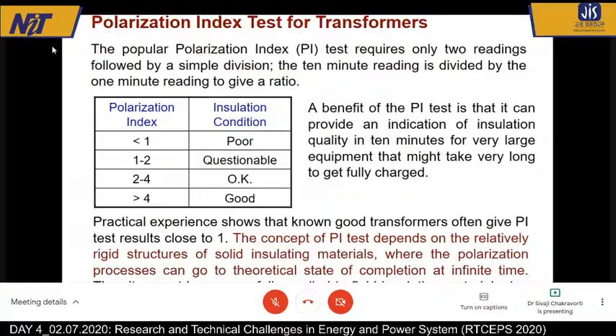Now, typically, when you connect the Megger to an insulation or any equipment, generally a certain DC voltage is applied to the equipment. It could be 500 volts to 5000 volts. So when a voltage is applied, the insulation gets charged. And when it gets charged, the charging current gradually decreases. It measures the voltage applied and the current, and then divides to get the insulation resistance. So it is quite expected that current at 1 minute will be higher and at 10 minutes will be lower.